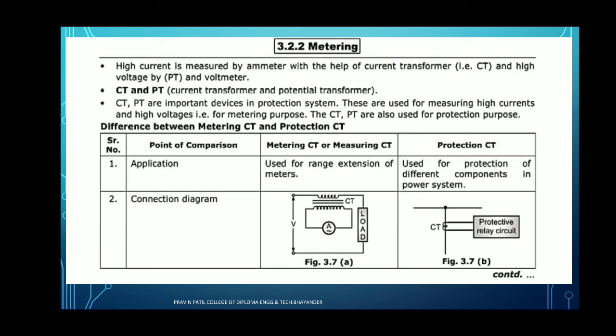Now we have to see the difference between metering CT and protection CT. The first point for comparison is the application. Metering CTs or measuring CTs are used for the range extension of the meters. If we have to extend the range, then the metering CT or measuring CT is applicable. Protection CTs are used for protection of the different components in the power system. Then the protection CTs are applicable.